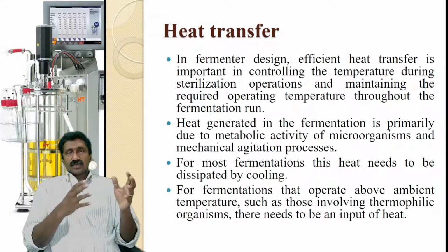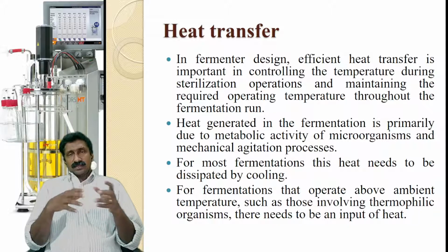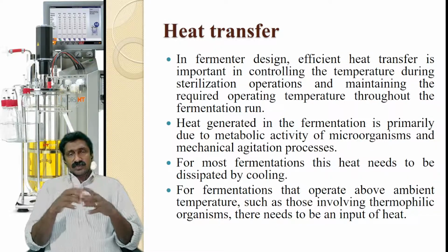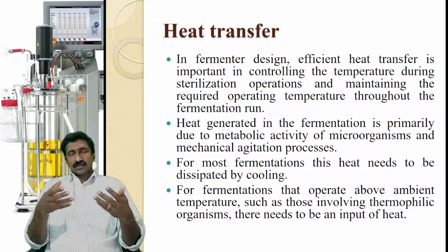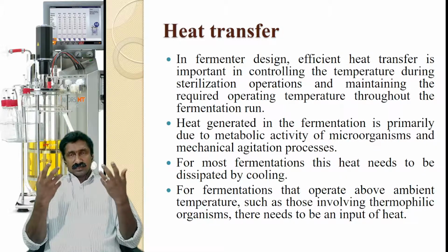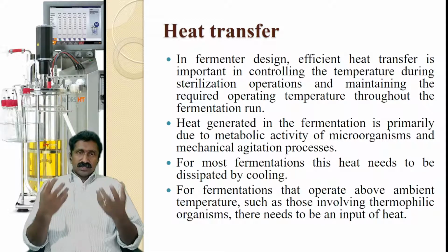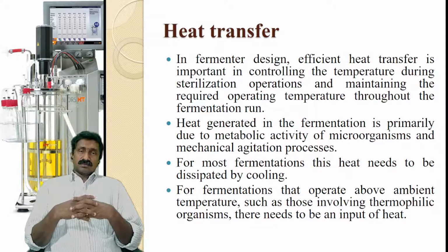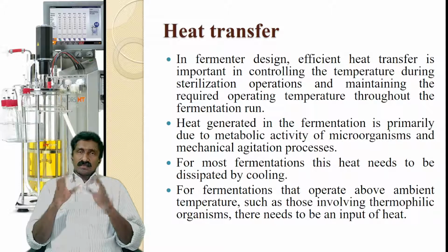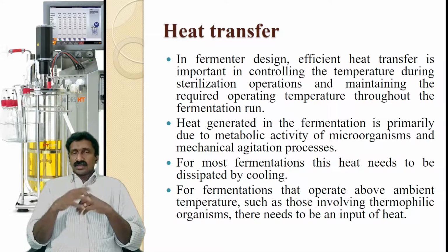That's one part where heat is required. And the second one is the overall fermentation process, in which the heat generation by the fermenting organism in the medium needs to be addressed. So basically, in a fermenter design, we have to take these two things into consideration.